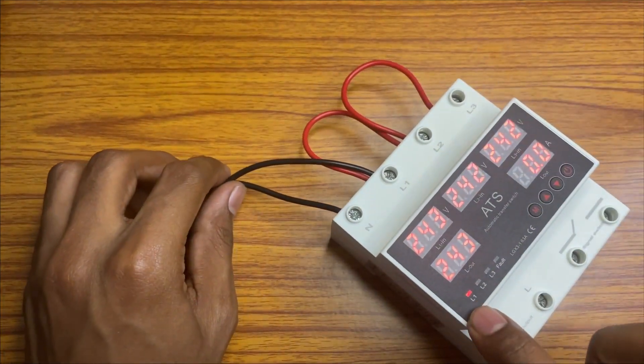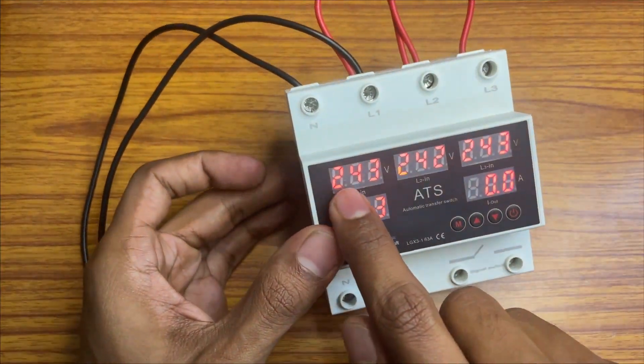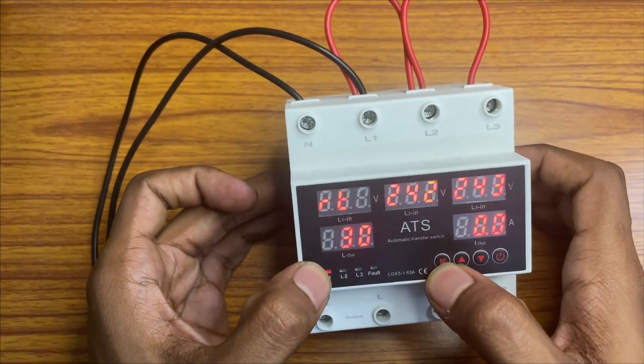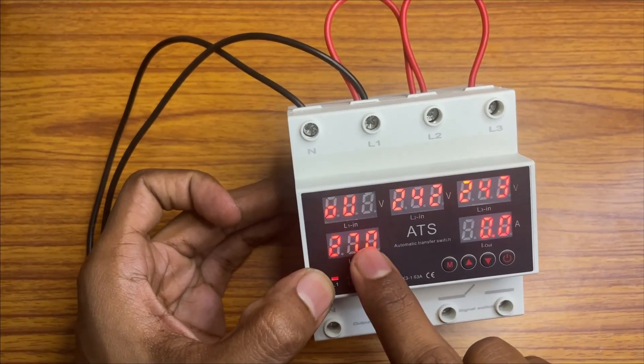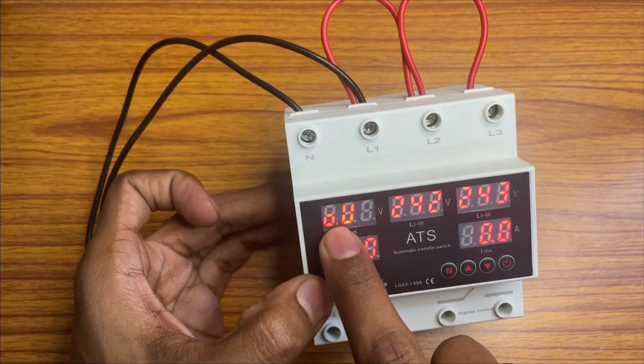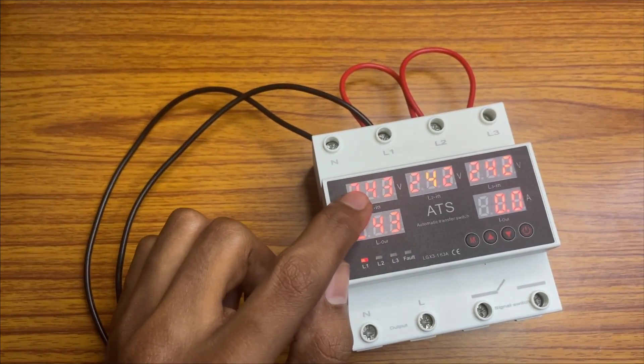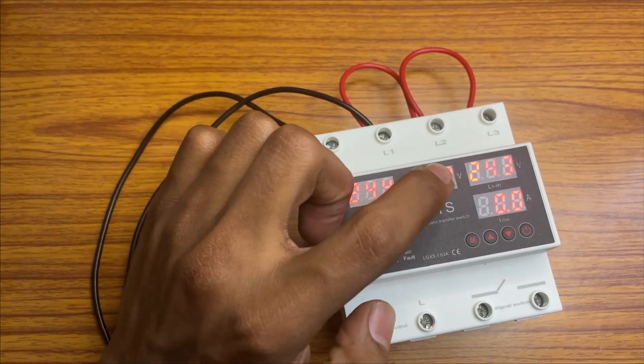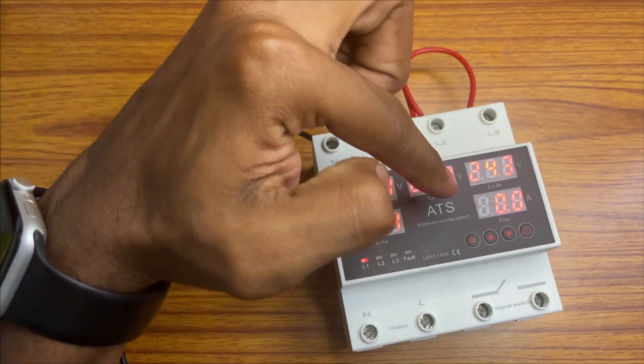Now it is giving the output from L1 as you can observe. Here we have set the voltage. If you press the M button: power delay time, reset delay time, over voltage. Over voltage 270 - if 270 in any one of the phase is coming, like for example L1 270, it will detect this is over voltage and it will jump back and give output from second phase. In that second phase it will show L2. For example if there is no line for L2.